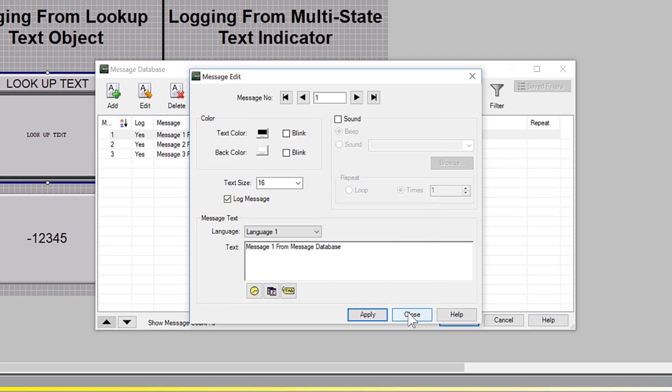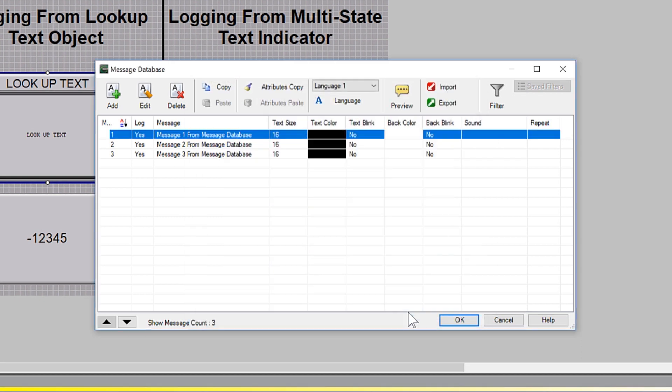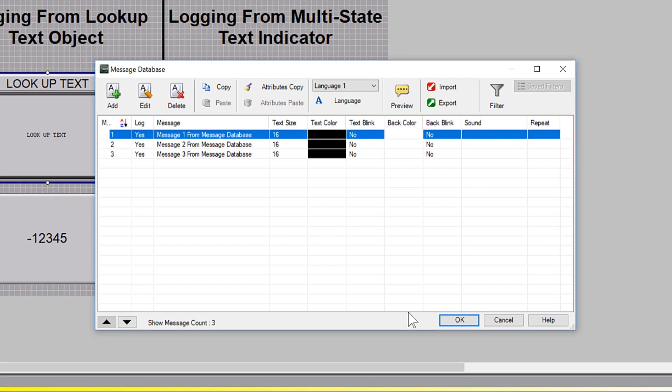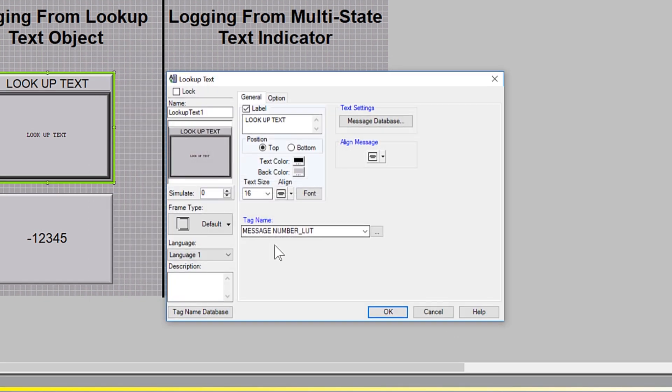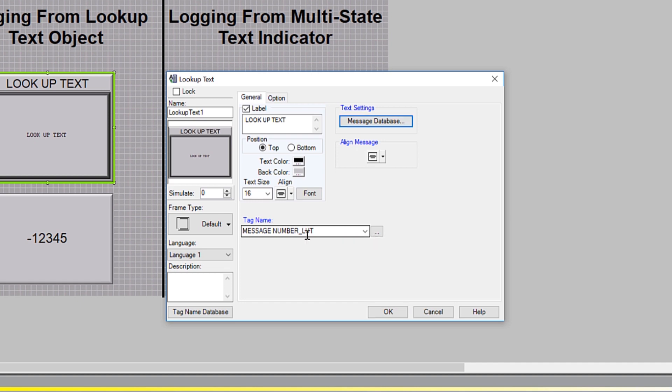Once the message is created, notice that there is a message number here. To trigger this message, the numeric tag using this Lookup Text Object must match this number for the message to display and then ultimately log if you have the logging function selected.